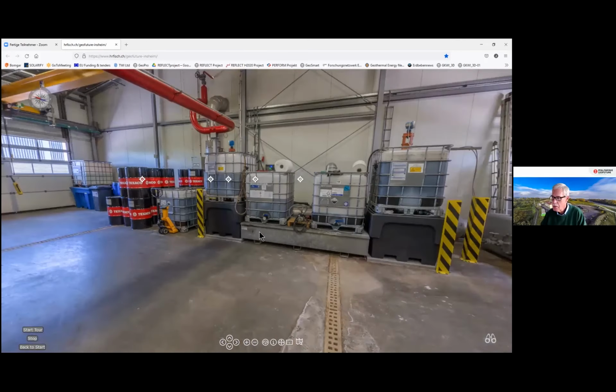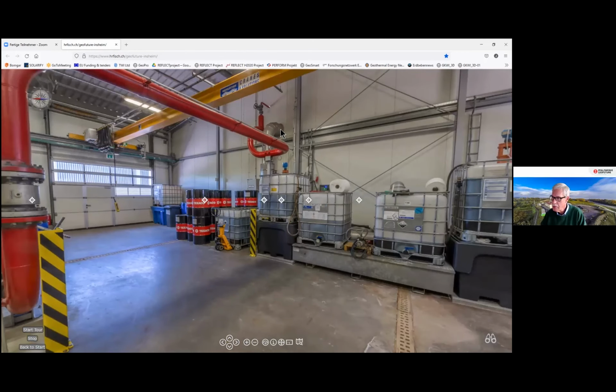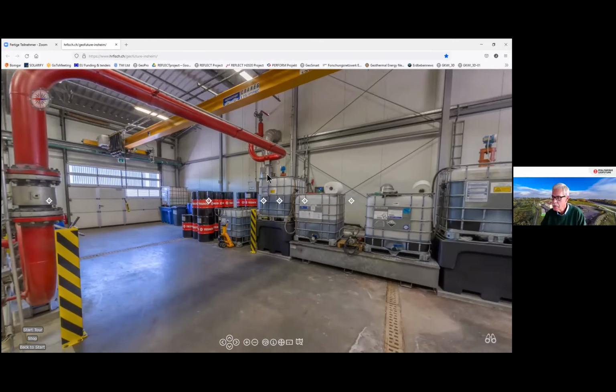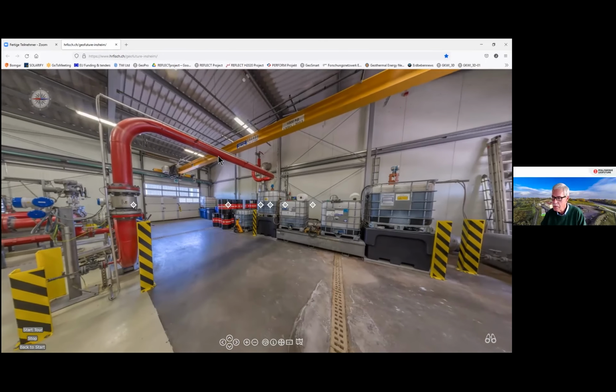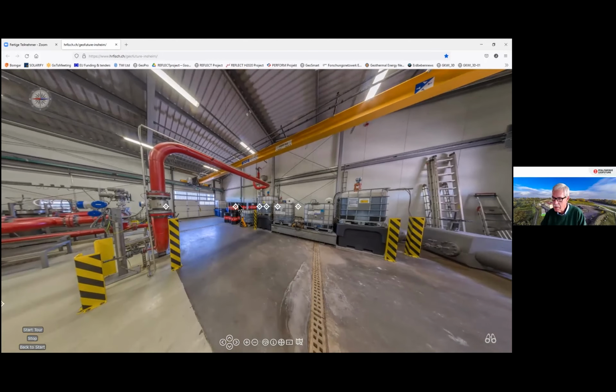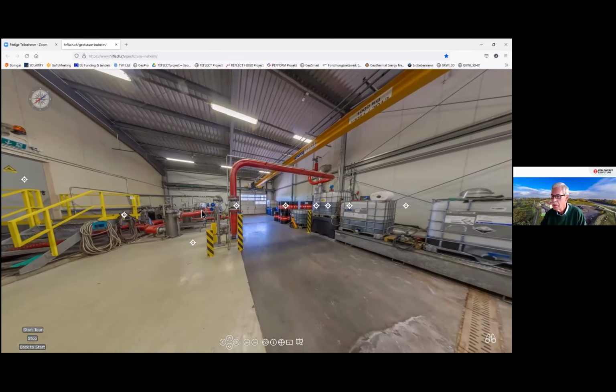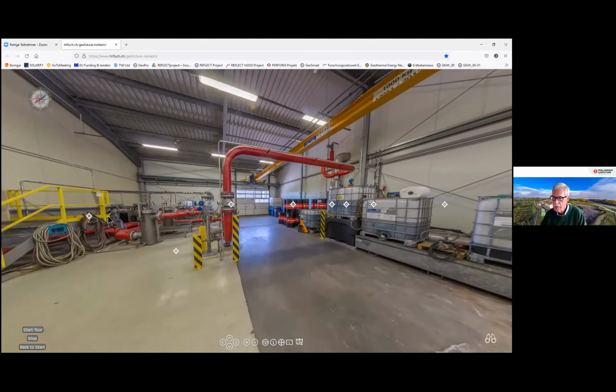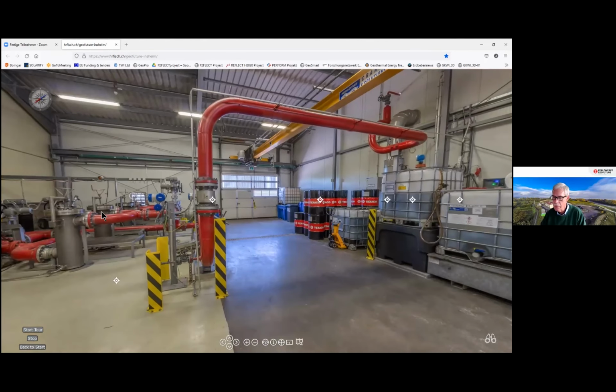The hot brine then enters the vaporizer we already saw outside. The cooled brine returns through the plastic pipe shown earlier, and is filtered again on this side. There we have more filter stations - 4 filters, 2 double filter stations, which frequently have to be maintained, as cooling down the brine in the heat exchanger group changes the brine pressure. We have these precipitation effects, and we want to prevent these scalings from reaching our reinjection well.